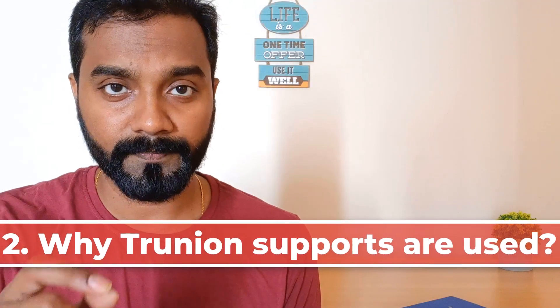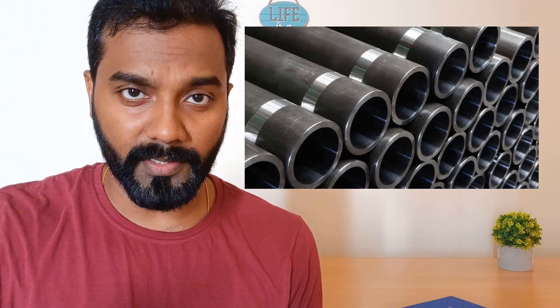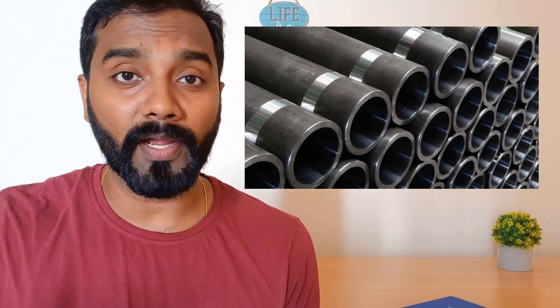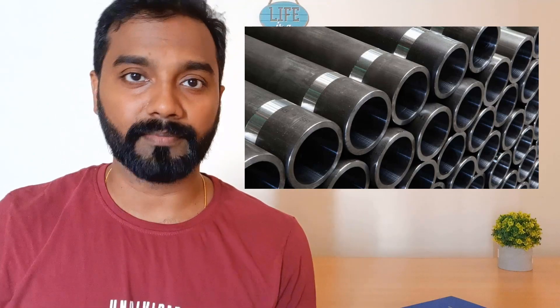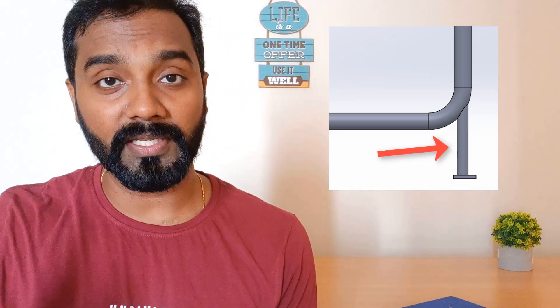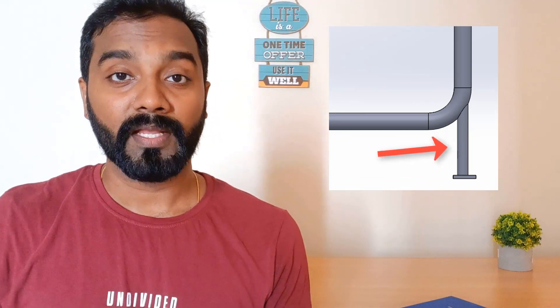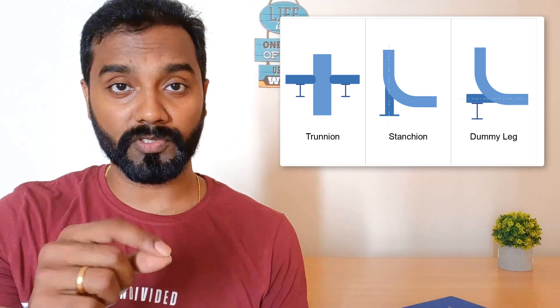Now let's move on to point number two: why are we using trunnion pipe supports in piping design, and why can't we replace them with any other support? Before answering, you have to understand something called optimization. In any project, we buy many different sizes of pipes, and during construction, lots of pieces of pipe are wasted. In order to optimize this wastage, you can use that waste pipe material as trunnion supports. This is one of the key factors why trunnion supports are used — you don't have to buy any additional material other than pipe.